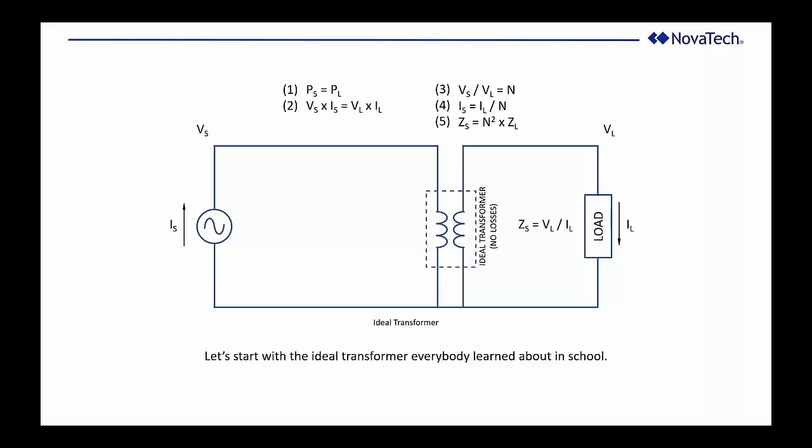That's the example we're going to do today. So, maybe on the primary side you've got 69 kV, and on the low side you've got 12,470. Of course, the relationship of the turns ratio to the current is the reciprocal of the relationship to the voltage. So high voltage, low current; low voltage, high current.